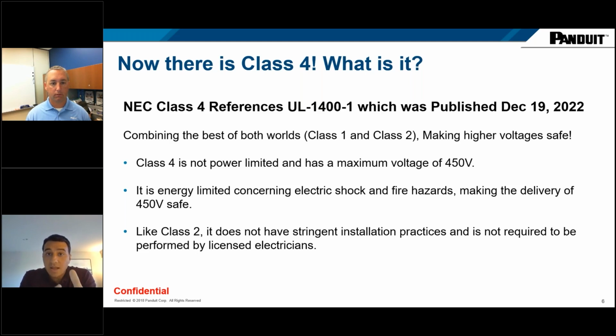So Class 4 is not power limited. It is what's called energy limited. It has a maximum voltage of 450 volts. And what I mean by energy limited, basically these systems are end-to-end systems, and you're trying to limit the amount of energy that a person gets exposed to or a particular fault gets exposed to. And if you're able to adhere to the requirements by this new standard, then you can be deemed safe, and therefore, based on local jurisdiction rules, you can be installed very much like Class 2 by low voltage contractors.